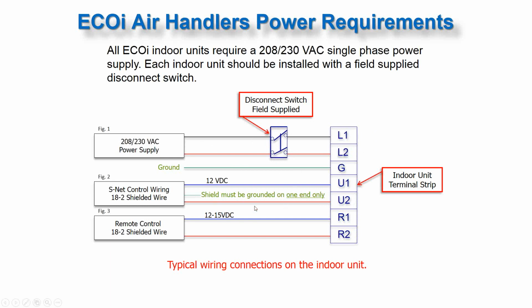Okay, so this is going to create our link from our condensing unit. Say our condensing unit is over here. We wire our condensing unit to all of our indoor units. So we wire from the condenser to the first indoor unit, and we connect to U1, U2. Then from here, we go to our next indoor unit and we go to U1, U2 as well, and all of the indoor units connected to a given system. And then in the indoor unit, you have R1, R2, and that is for your 18 gauge 2 conductor shielded wire that would wire to your wall-mounted thermostat or remote controller.